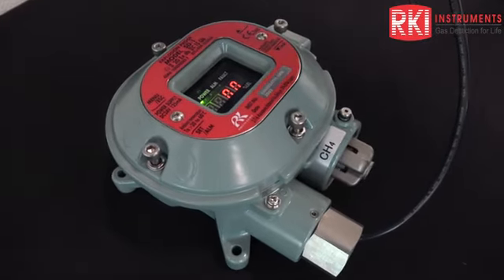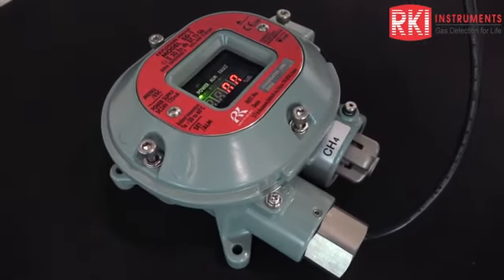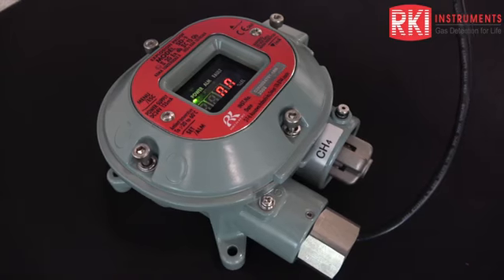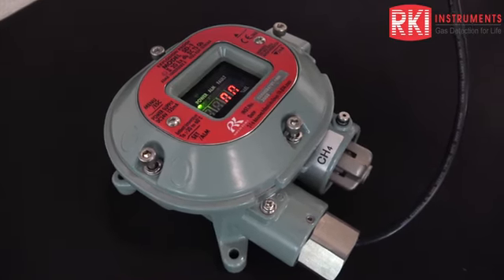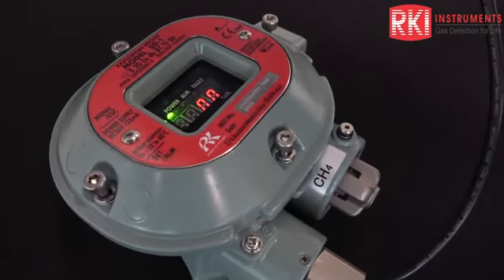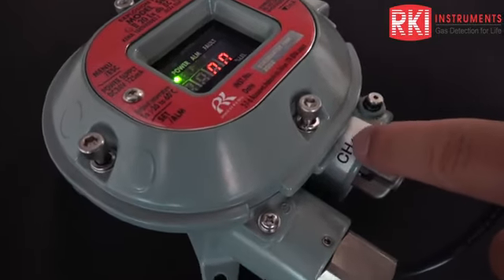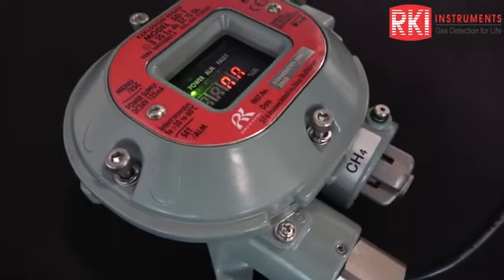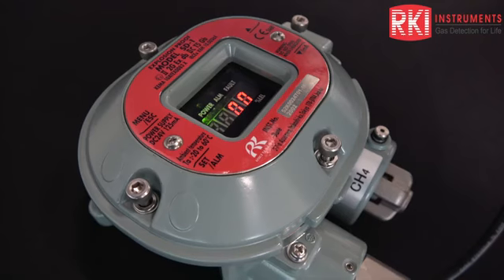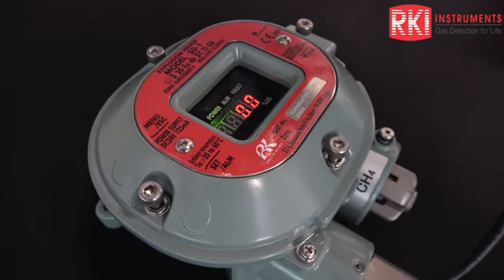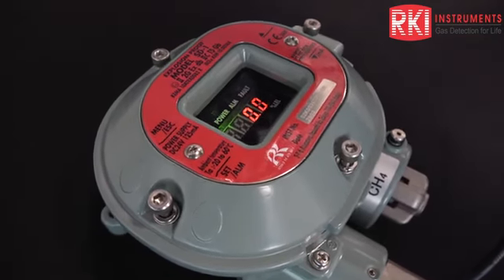Today we're going to cover the calibration of our SD1 explosion-proof detector head. And this head is set up presently for hydrogen gas, H2. You can see the CH4 methane label on here, but it can have sensors that can actually be calibrated to either hydrogen or methane, and we have other sensors for other gases as well.